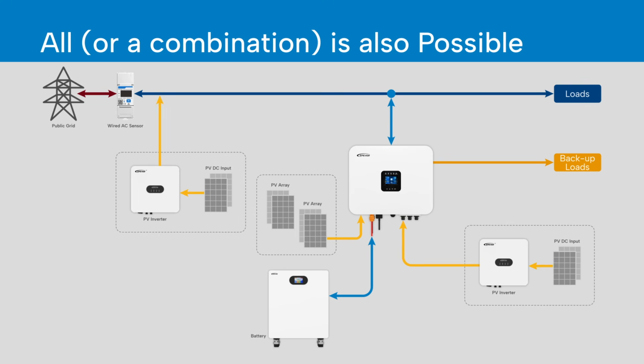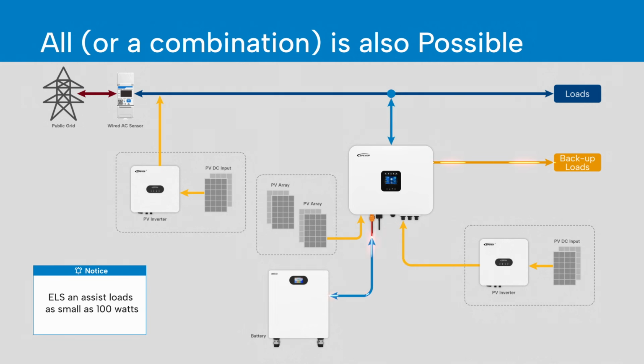Flexible combinations: all of these connection methods and combinations of them are supported. In regions with frequent or long-lasting outages, we often recommend combining AC-coupled PV, DC-coupled PV, and energy storage for maximum resilience. Additional notes: the ELS can assist loads as small as 100 watts. If the battery is sufficiently charged and the load is stable, the inverter will continuously output power to maintain a zero reading on the meter.